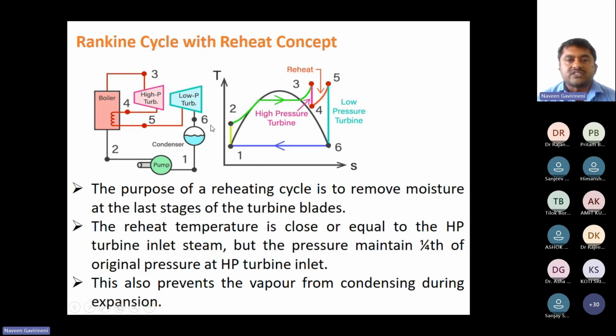So for that purpose, this reheating concept has been introduced. The line going from the turbine to the boiler is nothing but CRH, cold reheat steam. As per our power plant terminology, we call that the cold reheat steam. This condition is 37 kg and 337 degrees temperature. While going through the boiler, there is a reheater arrangement in the boiler. While going to the boiler, I could explain this clearly: what the reheating is and all the things.